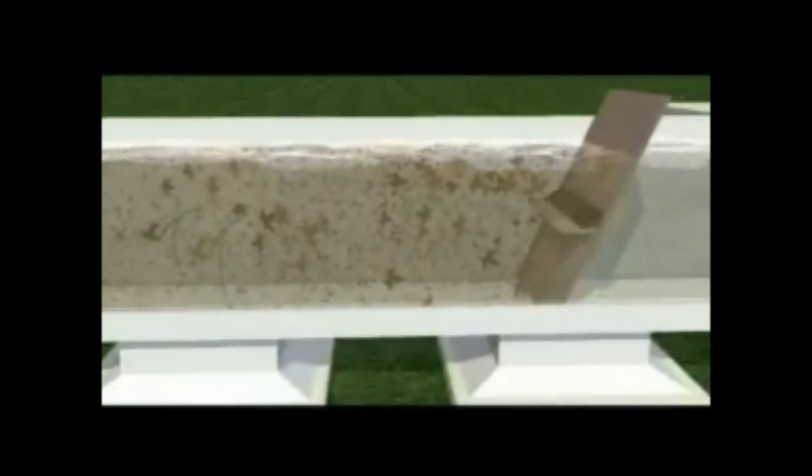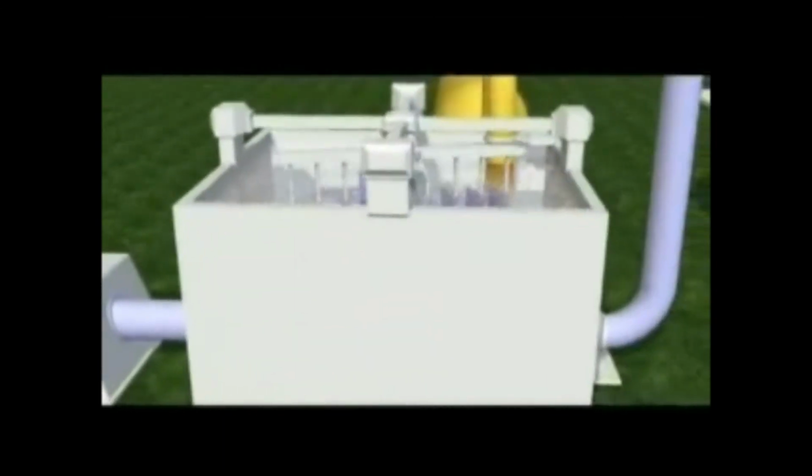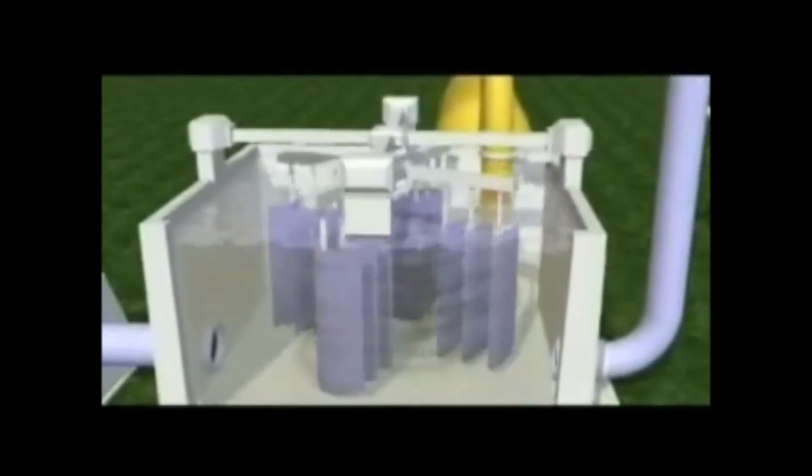The air takes some odours and gas from the water and allows some dissolved metal salts to separate to be filtered out. We add air by cascading the water down a tower, spraying it into the air or bubbling air through it. At this stage, there are still some fine pieces of matter suspended in the water, along with colour and bacteria. We add a precisely controlled amount of a coagulant like ferric or aluminium sulfate.